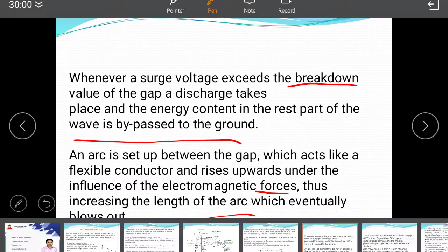So there are two major drawbacks of the horn gap. First is that the time of operation of the gap is large as compared to modern protective gear systems. Second is that if used on an isolated neutral, the horn gap may constitute a vicious kind of arcing ground. For these reasons, the horn gap has almost vanished from important power lines.